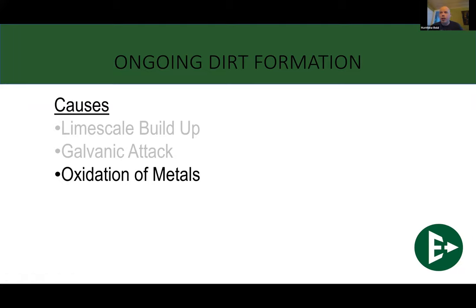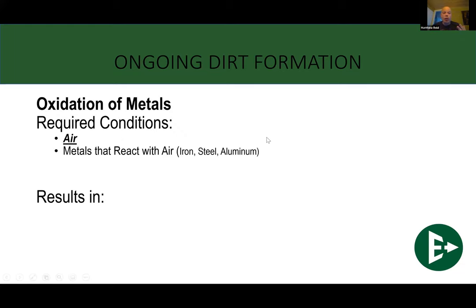The most standard pumps in the world, your Grundfos 1558, 2699, your Taco 007s, 0013s, and now they're 0015s, 0018s. Still, if you have a cast iron volute, that's still ferrous metal inside of a system, and it's still going to be subject to oxidization. Now, if you're doing your system in all copper or all PEX or stuff like that, you are limiting the amount of ferrous metal, but you're still usually having it in there with the pumps. So oxidization happens, and it's quite easy to make it happen. All it requires is air and metal that reacts with air. That's it. And what do those two things make? This.